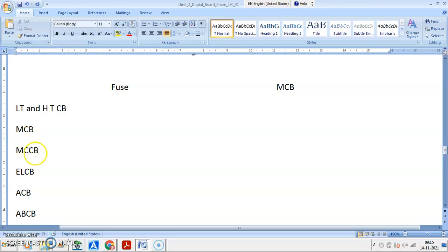You are having the industrial use also for MCCB. Again same as that of MCB, air as arc quenching media, low voltage operation up to 600 volts. Molded case frame, tripping mechanism. You are having electronic circuitry. Application LV circuits or LT circuits. These are long lasting, high mechanical strength, high dielectric strength than that of MCB.